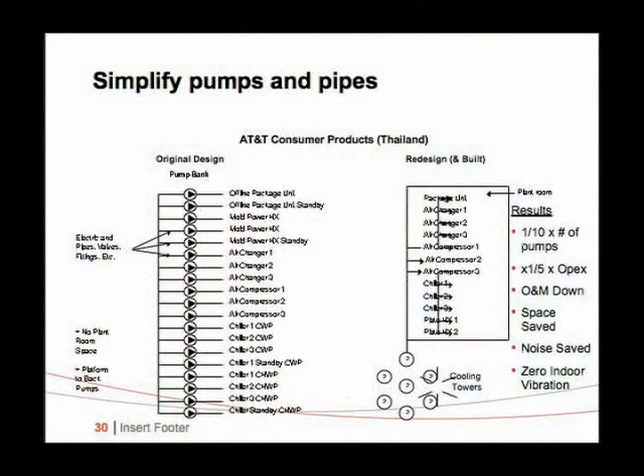This is AT&T Thailand, and the owner came to us because we did AT&T Singapore, and he said, you know, Lee, we have to double deck the pumps because there are so many pumps. So what is the answer? We put all the cooling towers outside. We reselected all the equipment to have equal, almost equal pressure drops, two pumps. So we have 20-something pumps down to two pumps, less space, less time, less cost, higher efficiency, et cetera, et cetera.